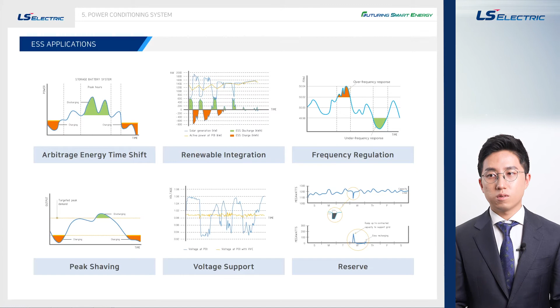Peak shaving is to use energy in daytime to save energy cost. Voltage support is to control voltage through discharging the battery. Reserve function is to support capacity load when there is a sudden drop in the load.